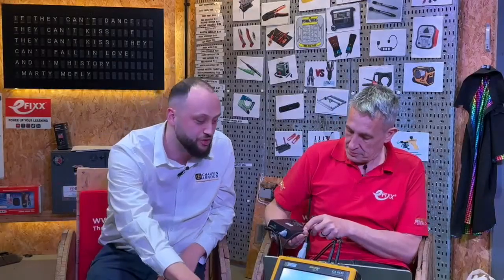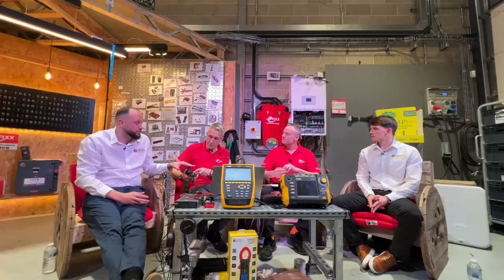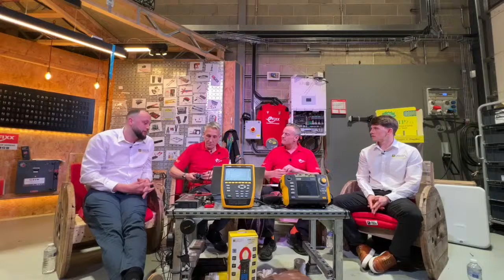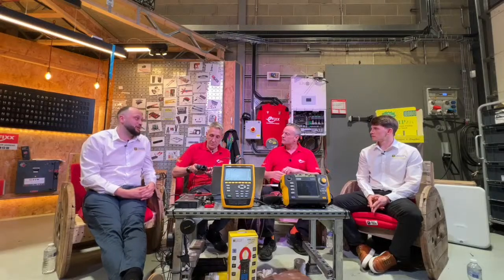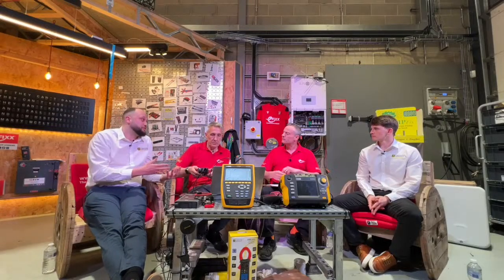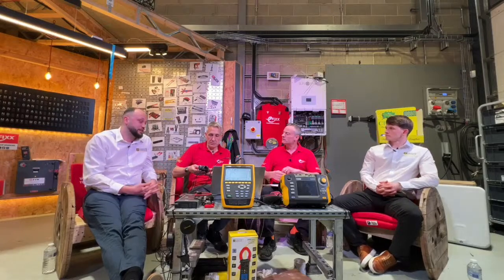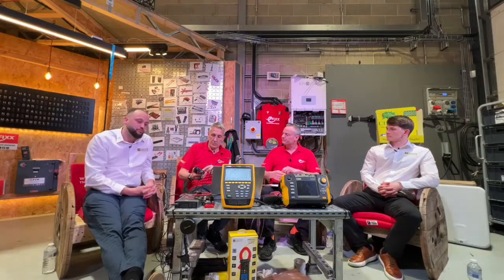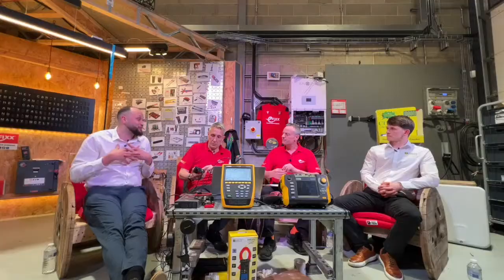I mean that's more for this unit - you can do load balancing with this, but you can't see it at the same time because it's only single phase, so the PEL 51 predominantly won't be utilised for that. I personally wouldn't choose the PEL 51 for load balancing if it's a three-phase incomer. If I'm choosing, the PEL 113 would be what I'd go for, because obviously you can see the currents at the same time.